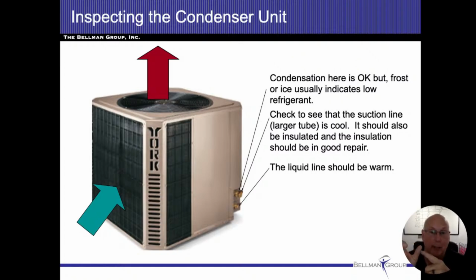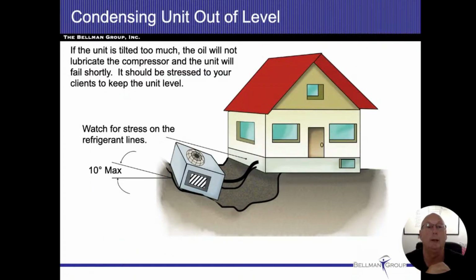And usually if you're going to have it there, you're going to also have ice forming on your indoor coil as well. Now, it's not always 100% true, all right? So we always want to do our best to see what we could see. But ice on an air conditioning system is not a good thing. That usually indicates low refrigerant, all right? I like to feel that the liquid line is warm and that the suction line is cool, and just do that on pretty much every unit when it's running.